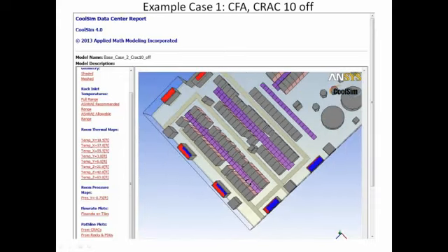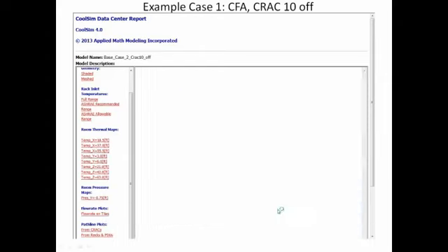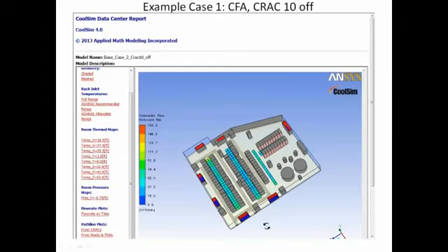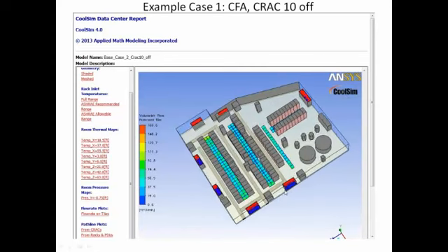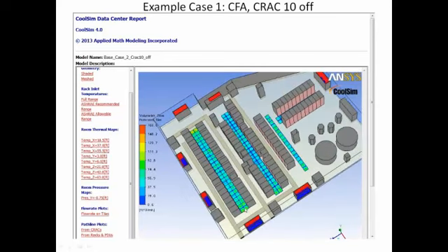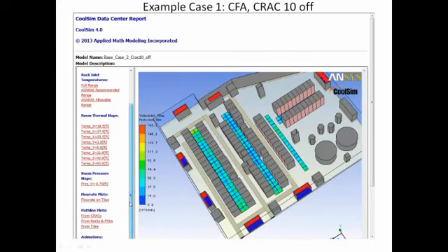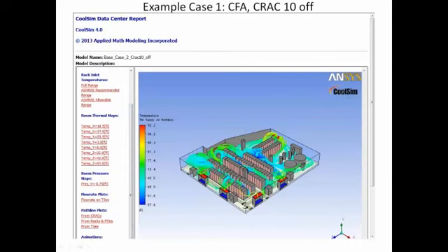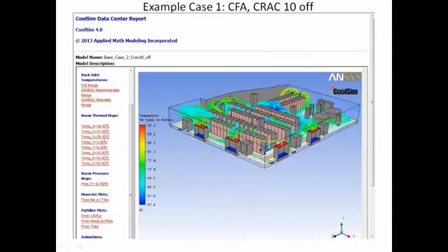Yep. You have very high velocity. That means that the static pressure in that raised floor is going to be very low, so there is not much air coming out of those tiles. Yes. You can see it in these plots here. Again, there's plenty of plots here to look at, but you see the airflow is not that good right in that region. And furthermore, if you take a look at the air coming from the tiles, you can actually see the bending of the air here, and I'll just zoom in tight.